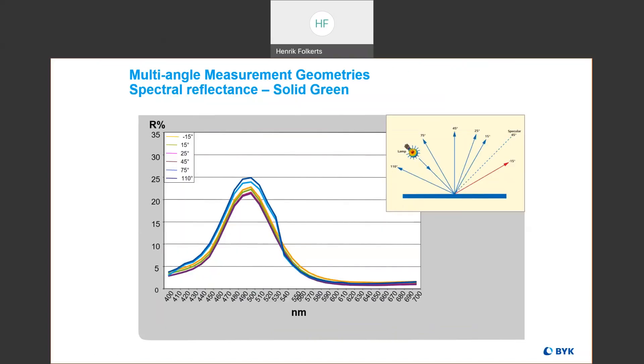Here we have an example of a multi-angle color measurement done with our BYK-mac multi-angle spectrophotometer. We can see six spectral curves — the spectral reflectance data obtained at each of the six measurement angles. For this solid green color, the curves are pretty much right on top of each other, indicating the color at each angle is going to be pretty much the same. Solid colors can typically be measured at just one angle to get an accurate color measurement.